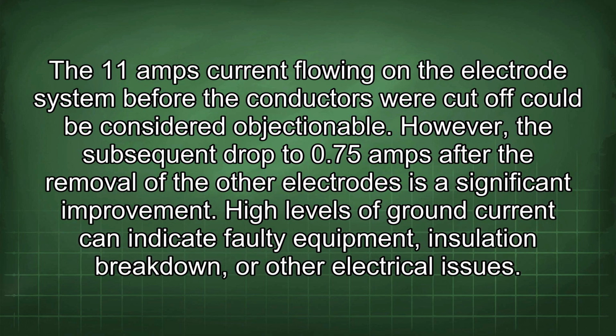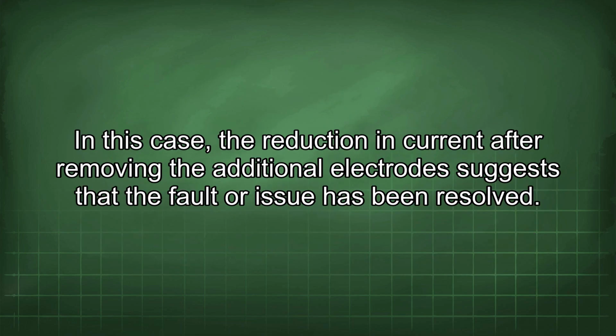The 11 amps current flowing on the electrode system before the conductors were cut off could be considered objectionable. However, the subsequent drop to 0.75 amps after the removal of the other electrodes is a significant improvement. High levels of ground current can indicate faulty equipment, insulation breakdown, or other electrical issues. In this case, the reduction in current after removing the additional electrode suggests that the fault or issue has been resolved.